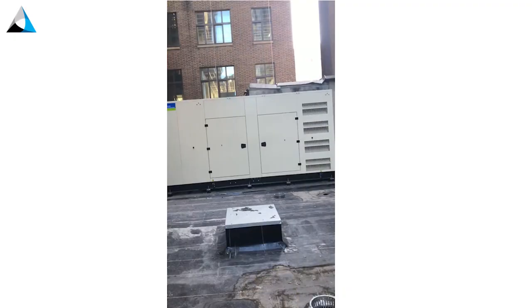This is a historic U-shaped building where the only place to put the generator was on the third floor inside of the U. To access it, they had to crane it over the 18-story building and drop it into place. I'm very sad I didn't get to see that. But from a commissioning standpoint: what if you have to replace or maintain the generator? There is literally no way to get a new generator in or out other than craning it over 18 floors.